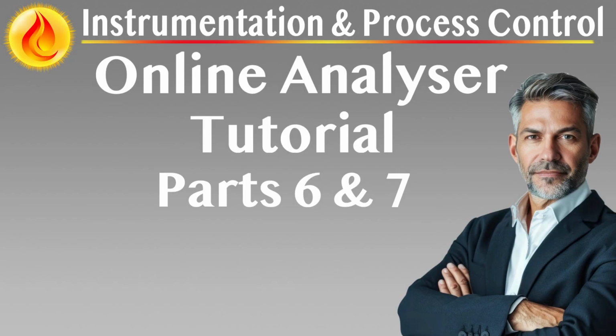Emergency shutdown and electrical isolation. Emergency shutdown systems must be available both locally, manual emergency stop push buttons, and remotely via DCS-SIS commands. Shutdown procedures should safely isolate power to all non-intrinsically safe devices, stop HVAC and sample handling systems, secure analyzer sample lines, maintain power only to safety-critical systems such as gas detectors and emergency lighting. Power isolation systems must be clearly labeled, easily accessible, and capable of handling locked-out conditions for safe maintenance.